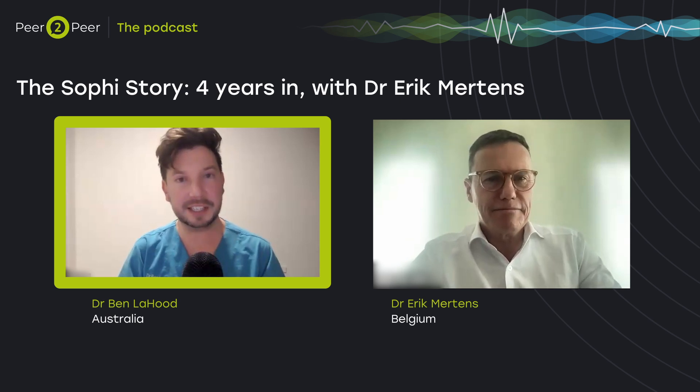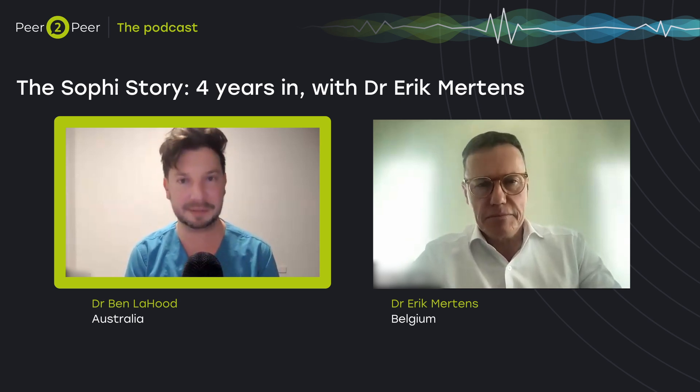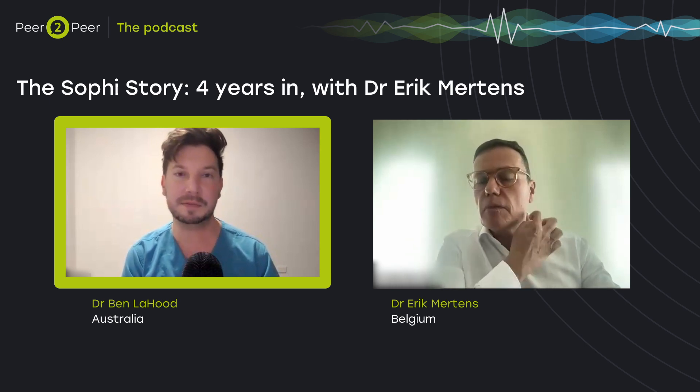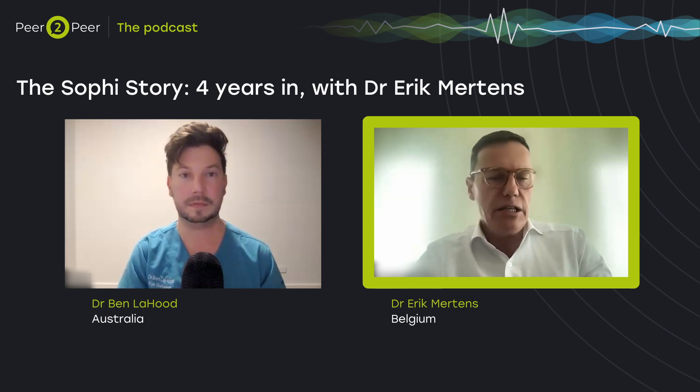Are you using much phaco energy, Eric? There's always a focus on reducing phaco energy, with machines using higher vacuum to dismantle the cataract while using less energy. What do you think compared to your previous machines? The Sophi system actually uses a sine wave of phaco power, meaning the absolute amount of phaco power entering the eye is reduced. The heating of the needle is lowered as much as possible while maintaining efficiency and a stable anterior chamber during the cycle. One day after surgery, when we see our patients back, we typically see clear corneas.